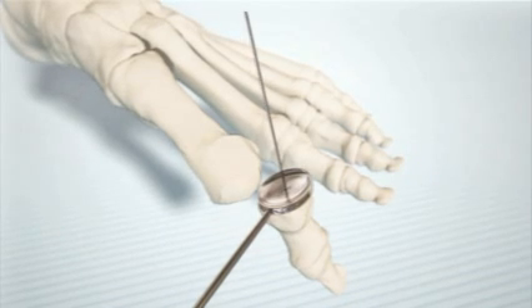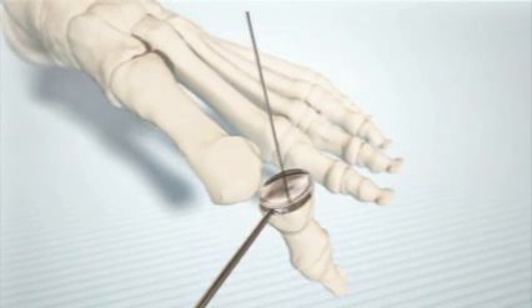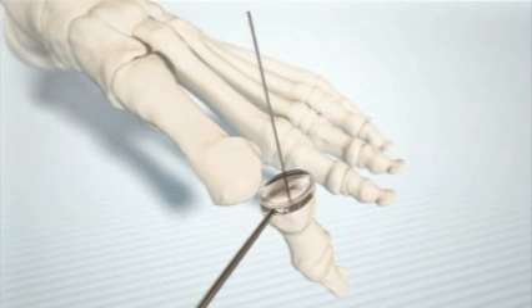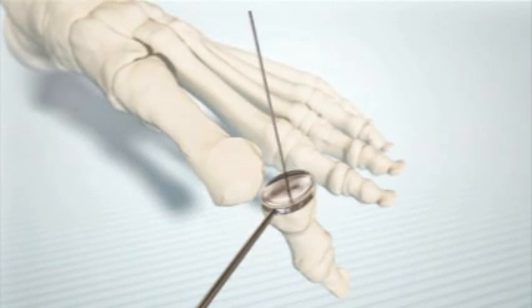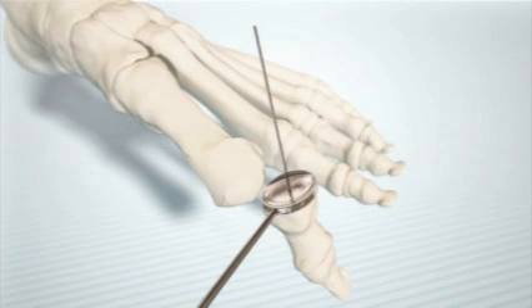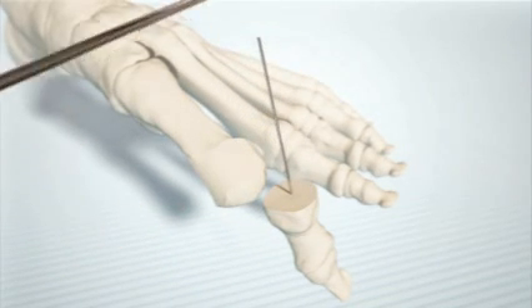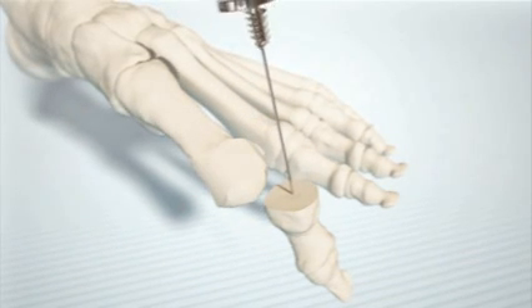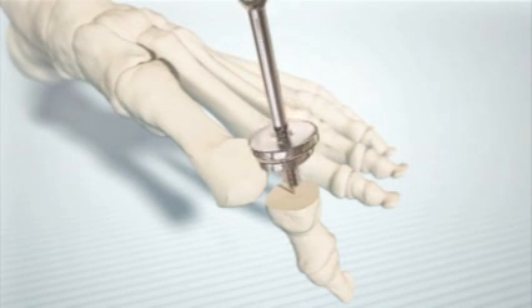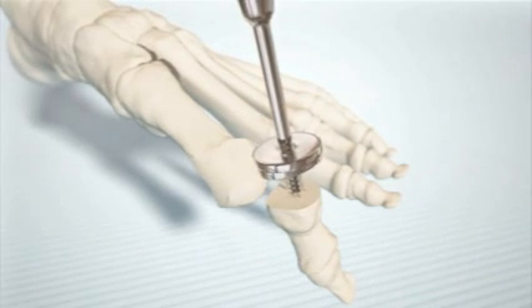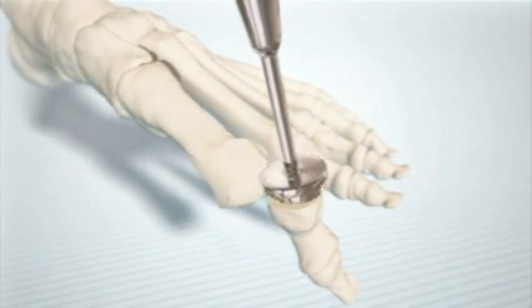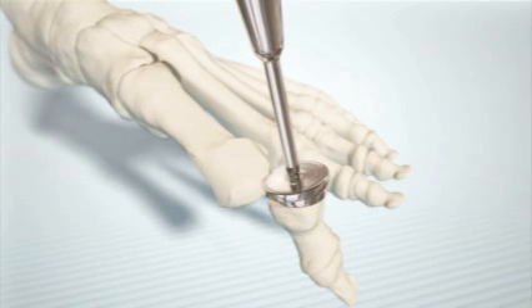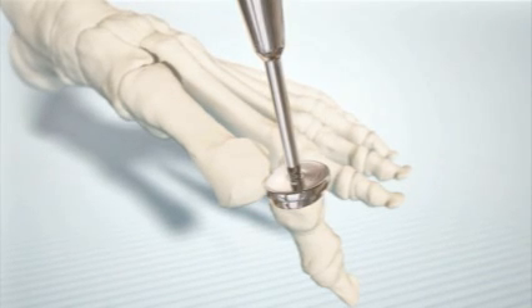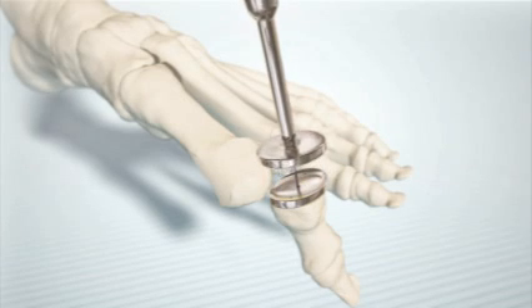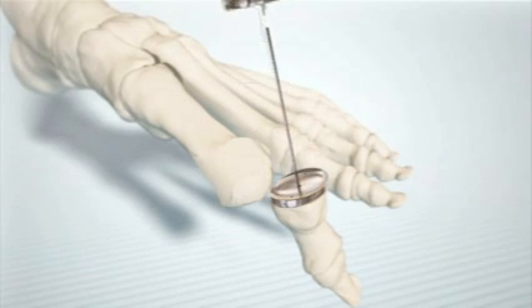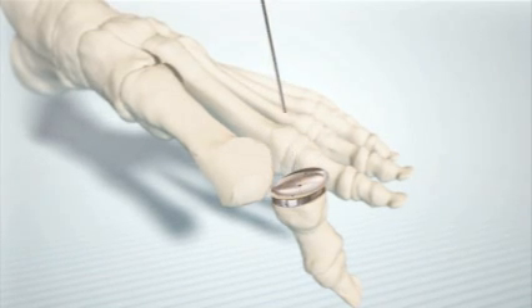This is the advantage of the cannulated system. There is no drilling or broaching, and thus the positioning of the implant is certain to be correct. Advance the K-wire another 20 millimeters. Remove the sizer and slide the corresponding hemi implant over the K-wire and drive the implant with the special 2-prong driver. Since the implant is oval in shape, its initial orientation may be inadequate. Advance the implant forward as much as 1/2 turn for correct orientation. Suture and close.